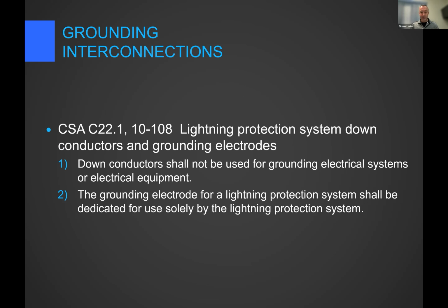You cannot use lightning protection down conductors and grounding electrodes for grounding of electrical or telecom equipment. We see cellular antenna people trying this all the time. They'll ground out to our stuff. Not so much Rogers or Shaw or the big ones, but smaller firms and other antenna installers will try and ground out to our lightning protection cable at roof level. Bad idea. Bad idea. If lightning does get on that, it can energize the antenna and fry out coax wires and circuits and all that stuff. Don't ground to our stuff.